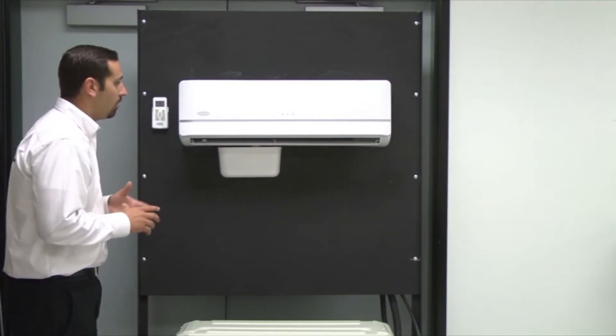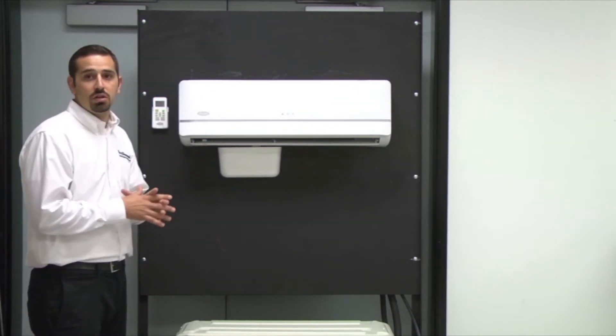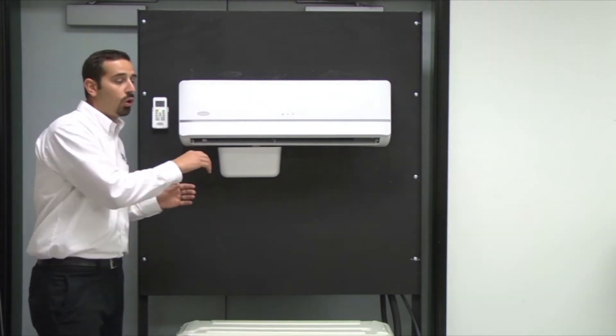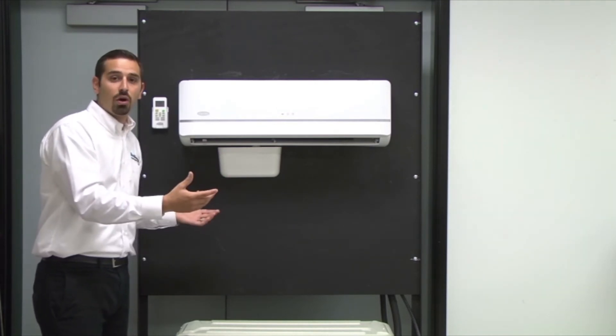All right, now we're all buttoned up. Pump's installed, tubing is ran. What we need to do now is test the unit. So while you're packing everything up, cleaning up your job site, if you want to just make sure you dump a little bit of cold water in the drain pan, that'll drain into the reservoir. The pump should turn on and eject the water.